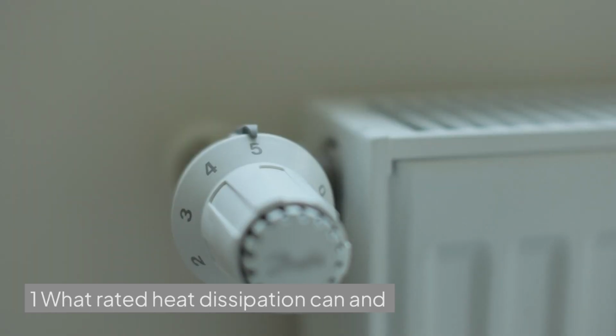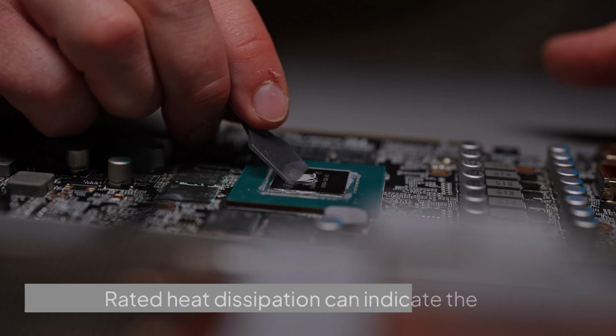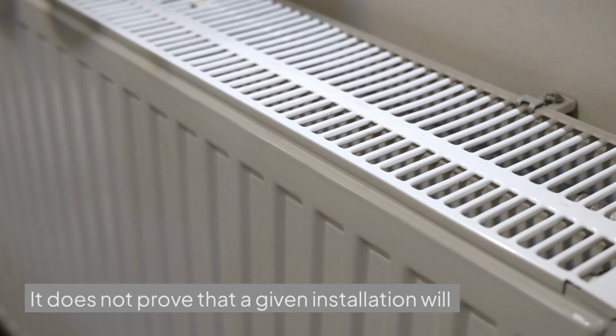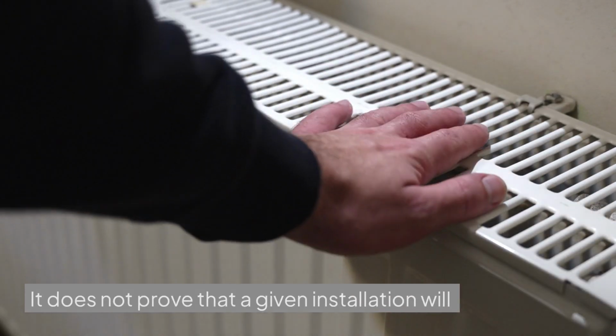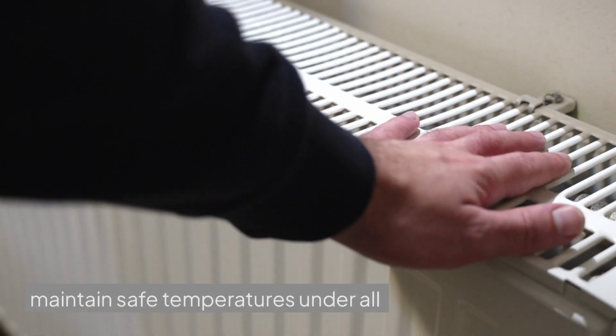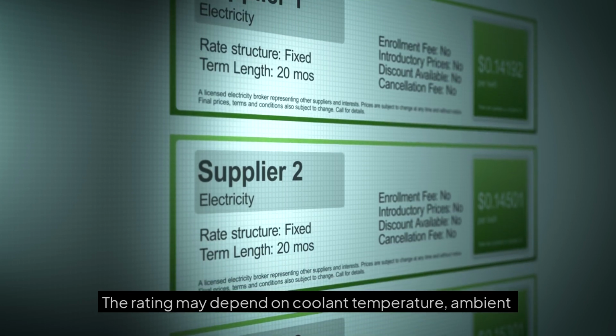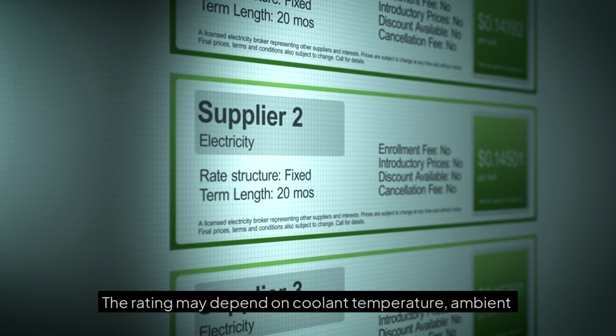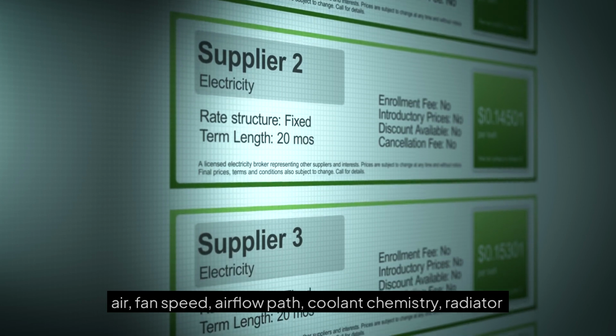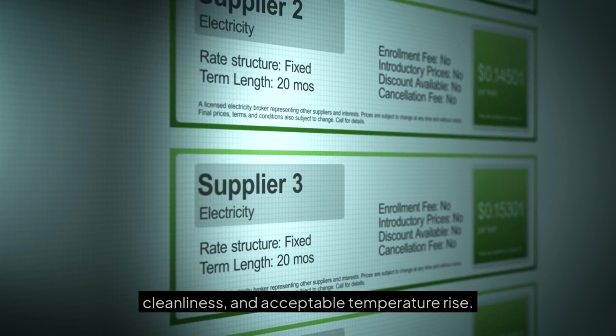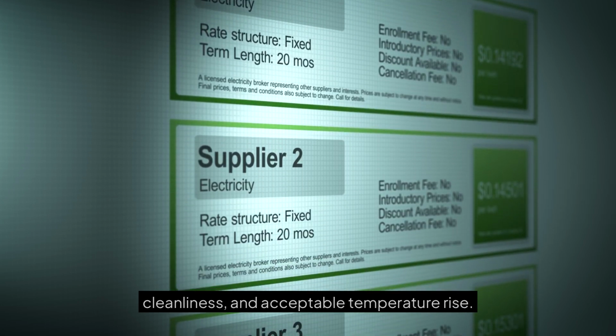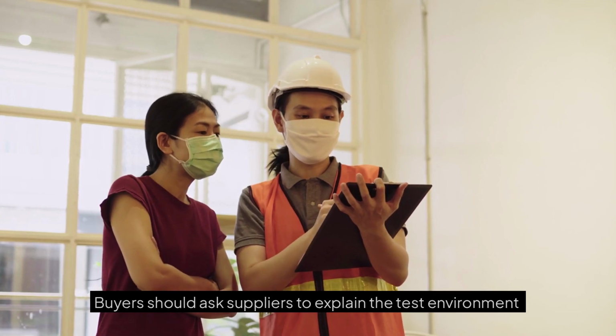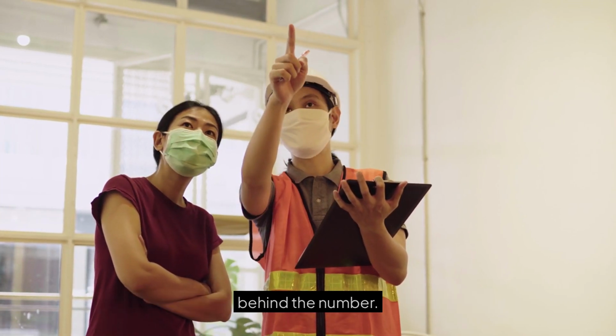1. What rated heat dissipation can and cannot prove. Rated heat dissipation can indicate the intended scale of a radiator. It does not prove that a given installation will maintain safe temperatures under all conditions. The rating may depend on coolant temperature, ambient air, fan speed, airflow path, coolant chemistry, radiator cleanliness, and acceptable temperature rise. Buyers should ask suppliers to explain the test environment behind the number.